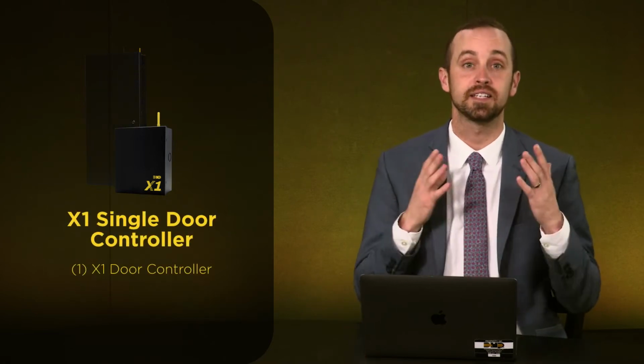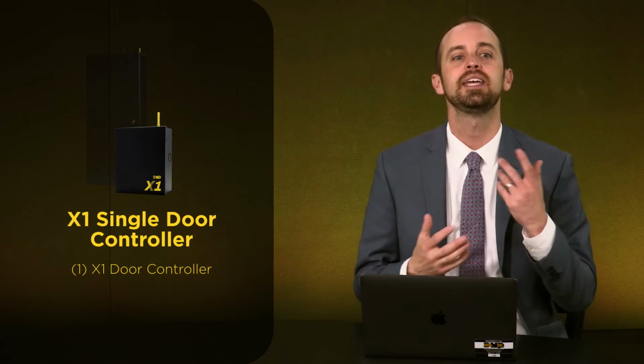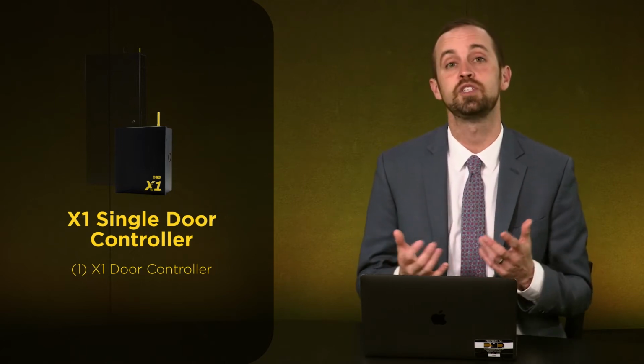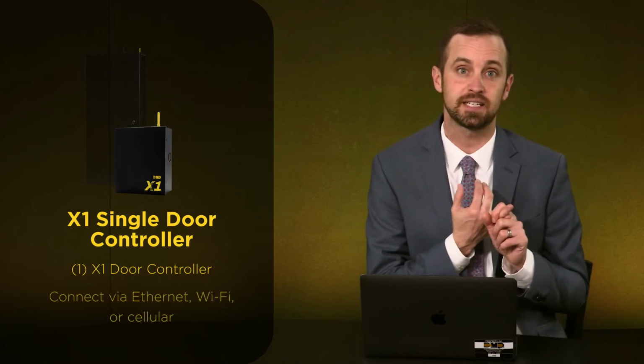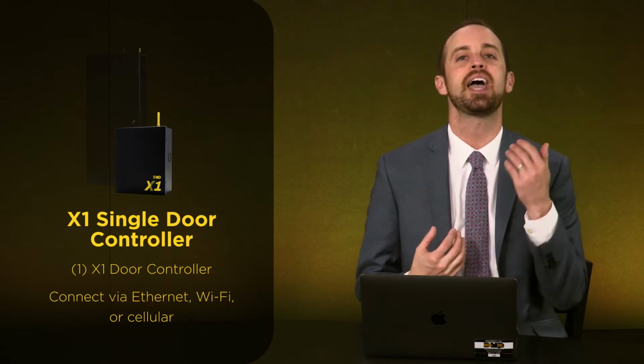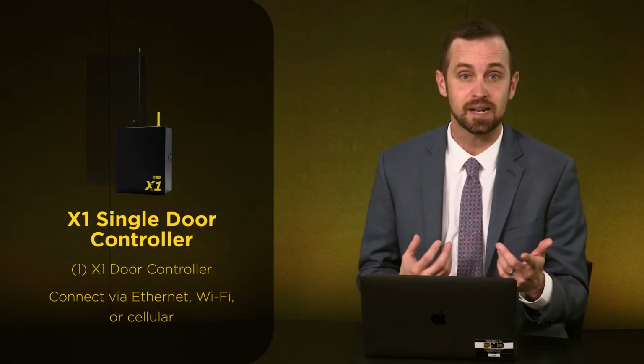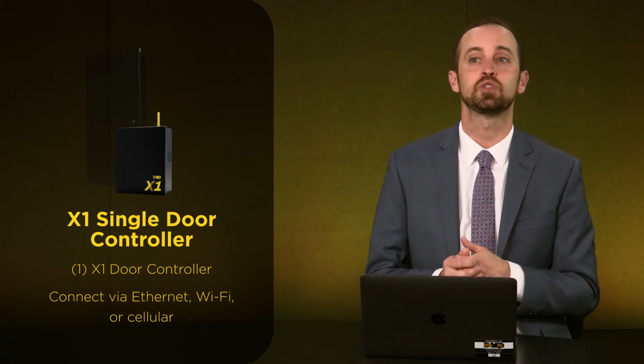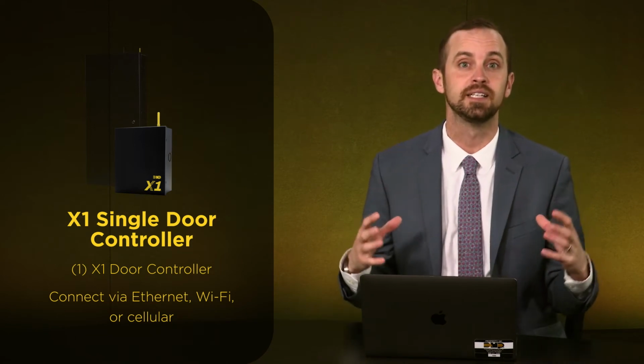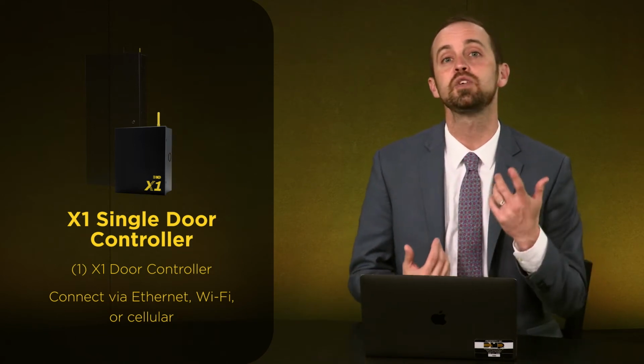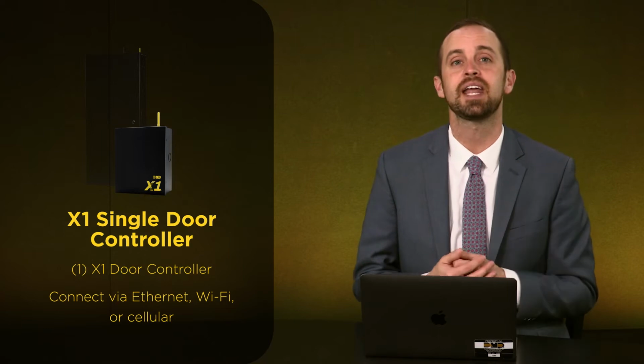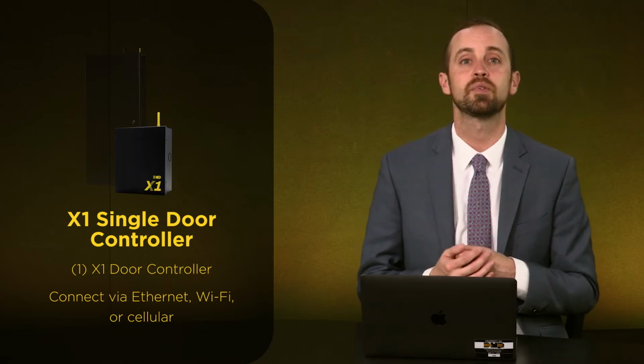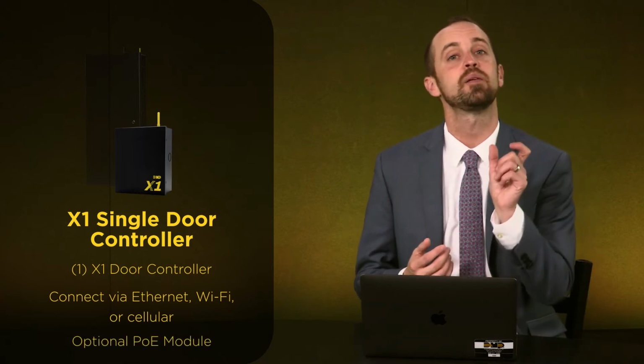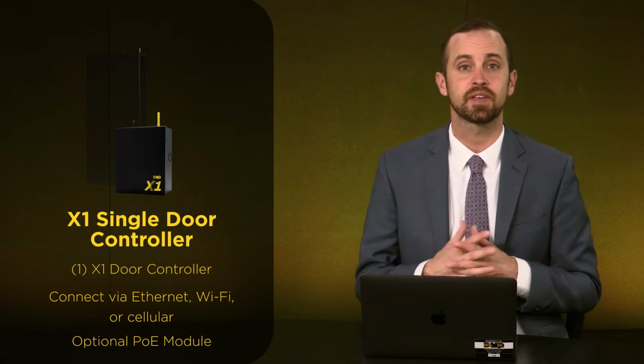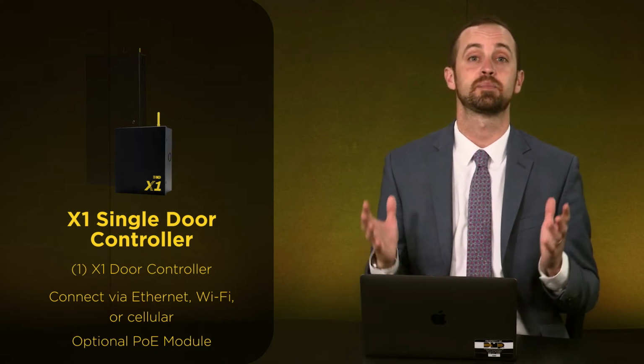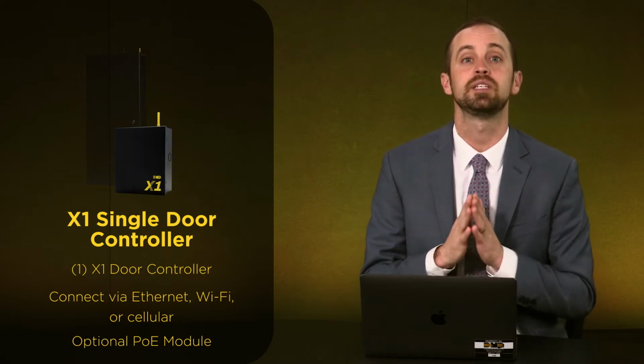Each X1 is a single door controller. Each X1 also provides you with Ethernet or Wi-Fi connectivity and the ability to add cellular either as a backup or for those applications where you might want cell only. So with X1, as long as you have power, you can have an access control door. Also, we provide you the ability to add on PoE. So if that's something that the customer's facility is able to provide, then you can power it using PoE.